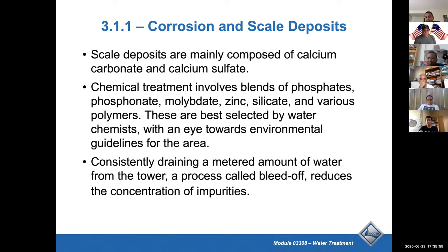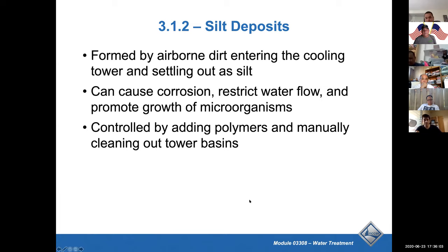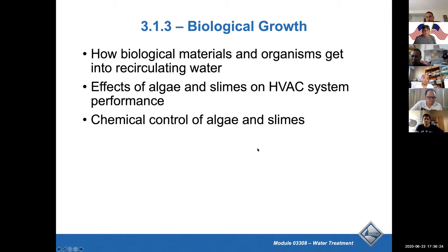The bleed off down here in the bottom, it's like a blowdown. Okay. Silt deposits are formed by airborne dirt entering the cooling tower and settling out as silt. It can restrict water flow and lead to growth of microbes, as it's a food supply. It's controlled by adding copolymers and manual cleanout, so you actually get in there and scrub it down. Okay.